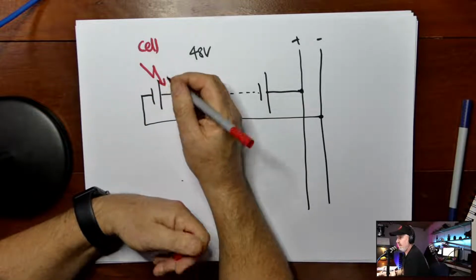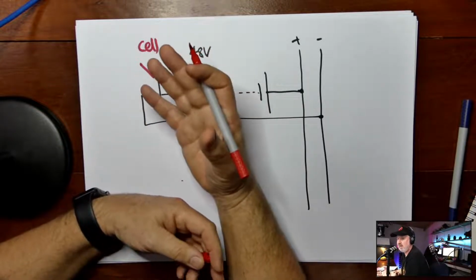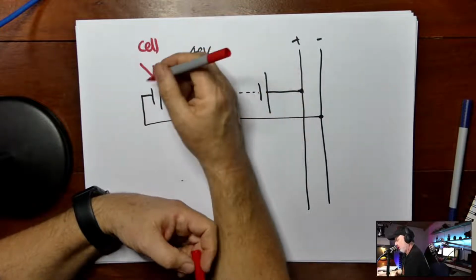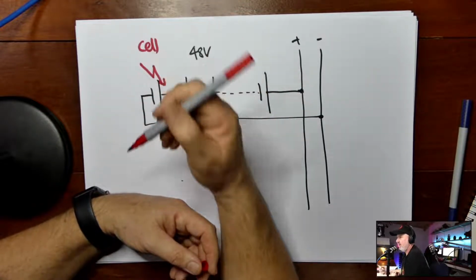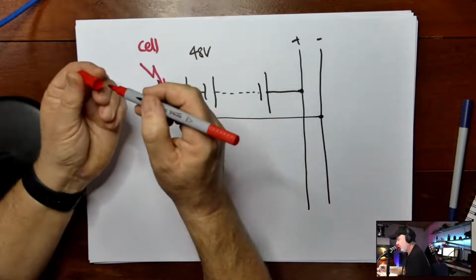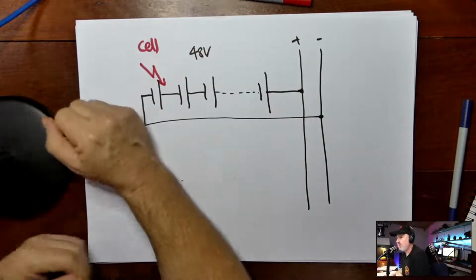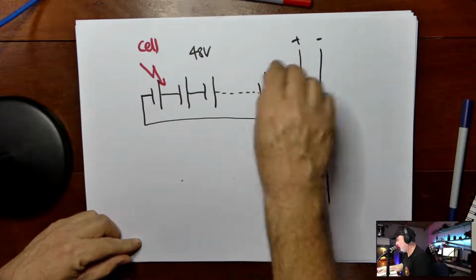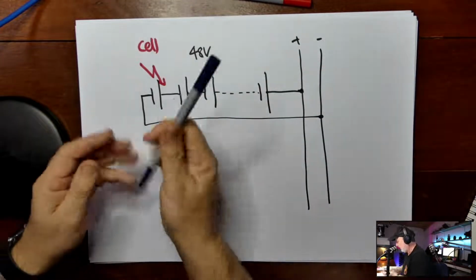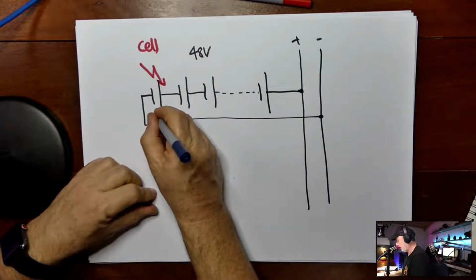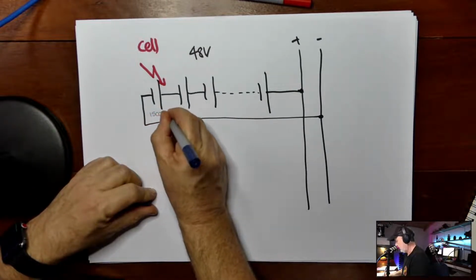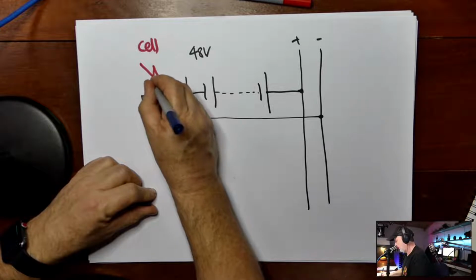Now, there's no overcurrent protection within the cell. This is just a lead acid battery. It's got 2 terminals, and in the case of those large ones, 6 or 8 terminals sometimes. So if you put a spanner across the terminals, you will get the bolted fault current at the rated capacity they showed. So if I go back to my spreadsheet, I'm just imagining I'm still using the same cells in this design here. So these are the 1500 amp hour cells, and it's a 2 volt cell.